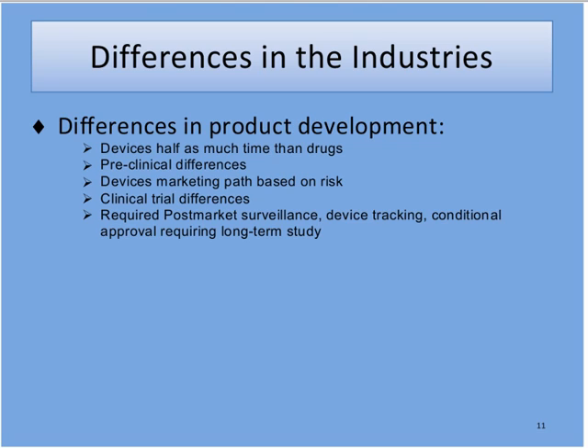Some devices are required to have post-market surveillance, device tracking. Back in 1993, the FDA passed another regulation, a device tracking regulation, saying that for any permanently implanted product, and a permanently implanted product is one that's implanted for 1 year or more, any permanently implanted product must be tracked by the manufacturer. In the event of a product problem, that a recall must be performed, the sponsor, or the manufacturer, must know who has those products implanted in them. So it's a regulation now that any permanently implanted product must be tracked, okay, for the life of the device or the life of the patient, whichever is shorter.